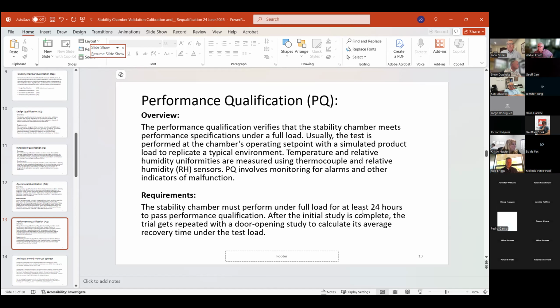Chamber must perform under full load for at least 24 hours to pass performance qualification. And after the initial study is complete, the trial gets repeated with a door opening study to calculate its average recovery time under the test load. So in this case, the PQ uses a simulated load, and I think there's probably room for a variety of interpretations as to what a full load is and what it should be composed of. I've seen it done lots of different ways.